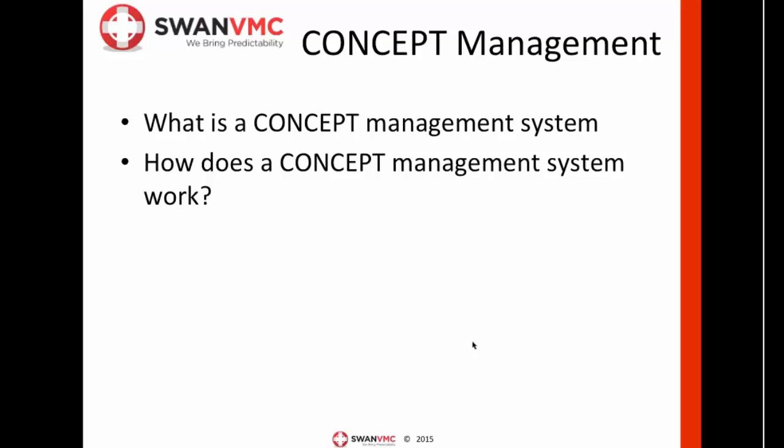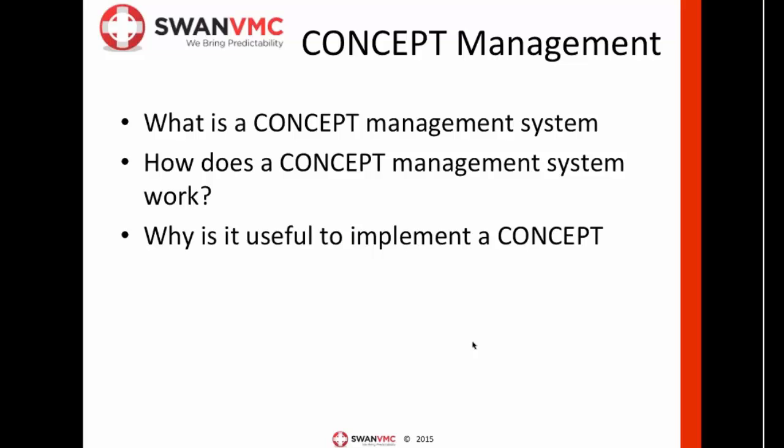These work items are then interrelated with relationship logic. So examples of relationship logic might include, in our space, verified or validated or causes, or perhaps refined. So examples: a hazard causes a harm, a requirement refines a user need, or a test case verifies a product requirement. So what we're trying to do here is provide these logical ideas and interrelate them.